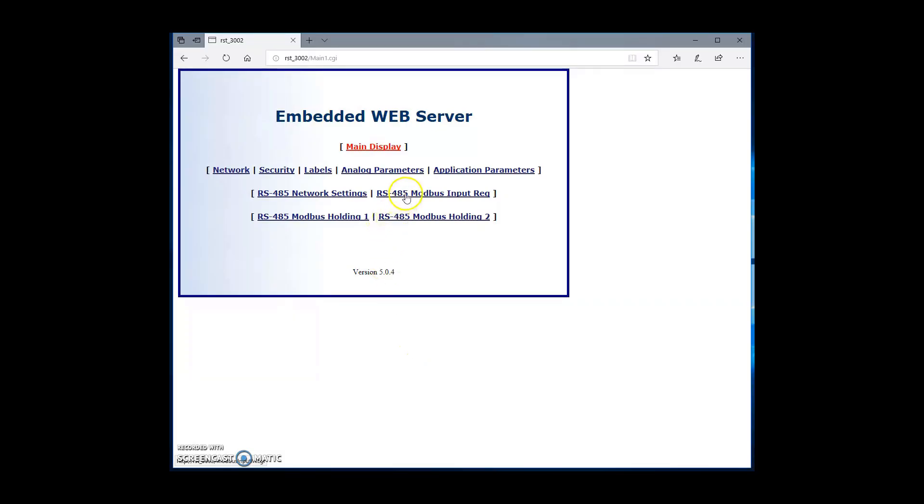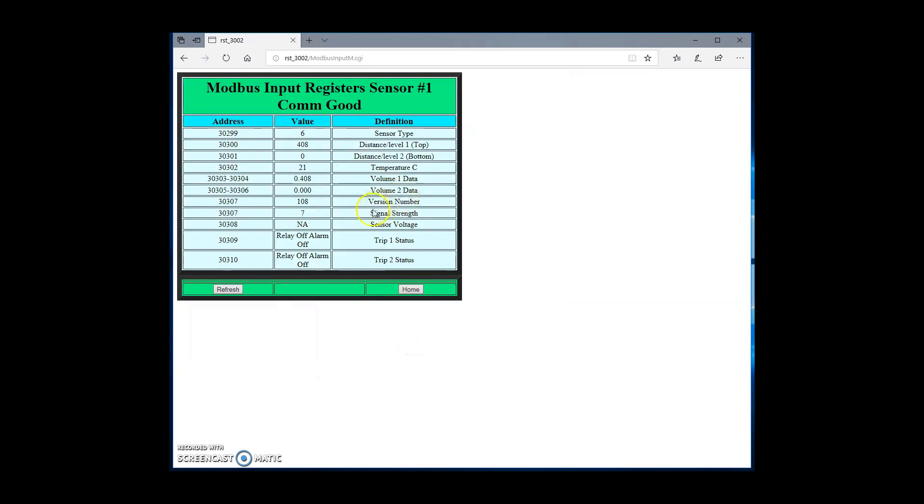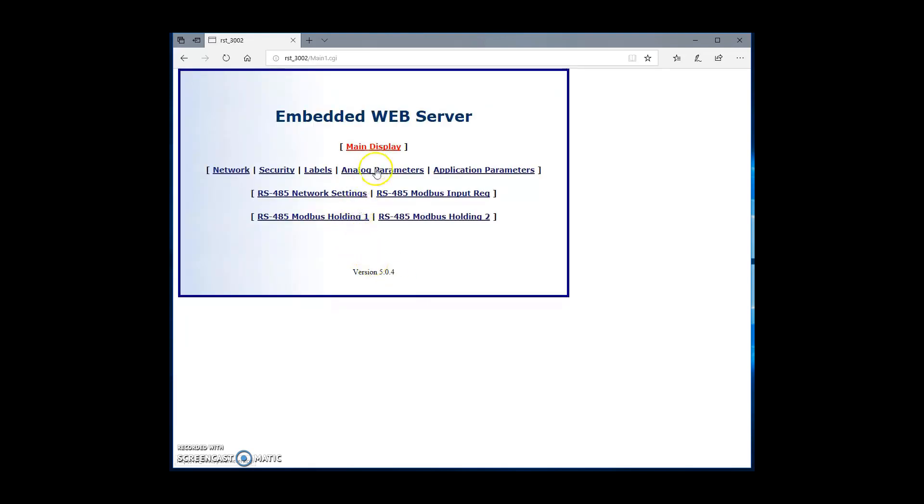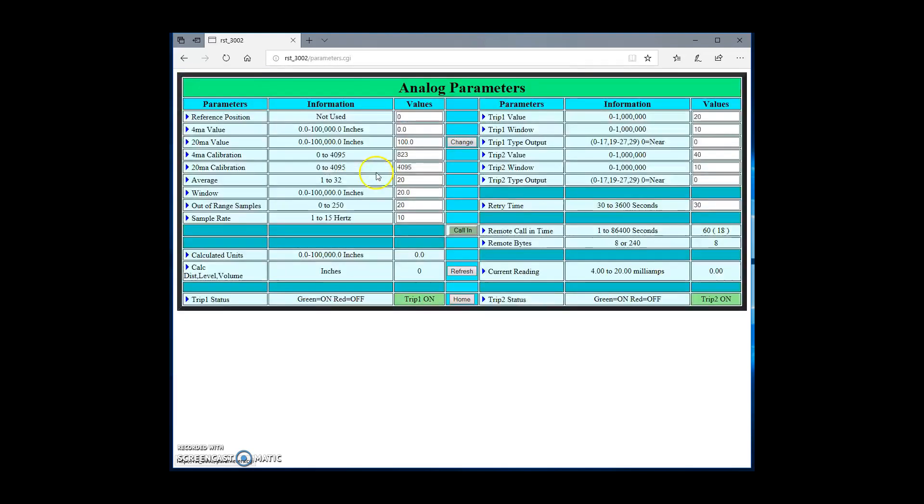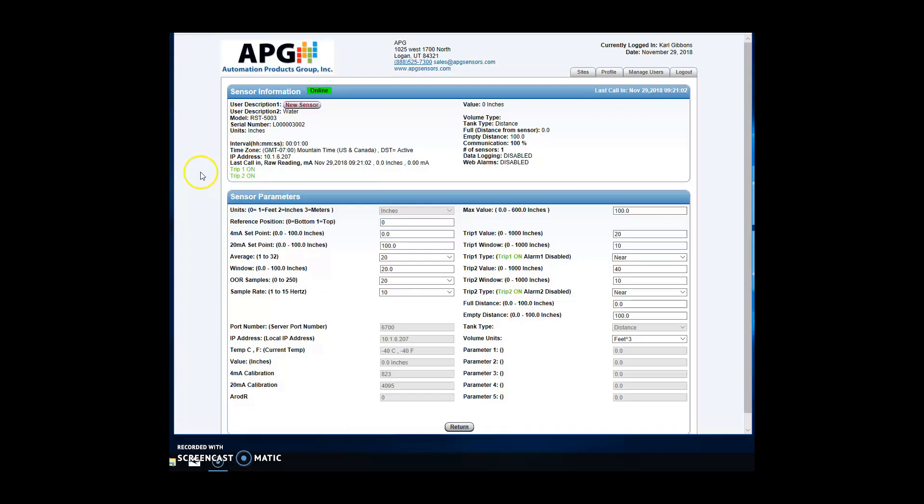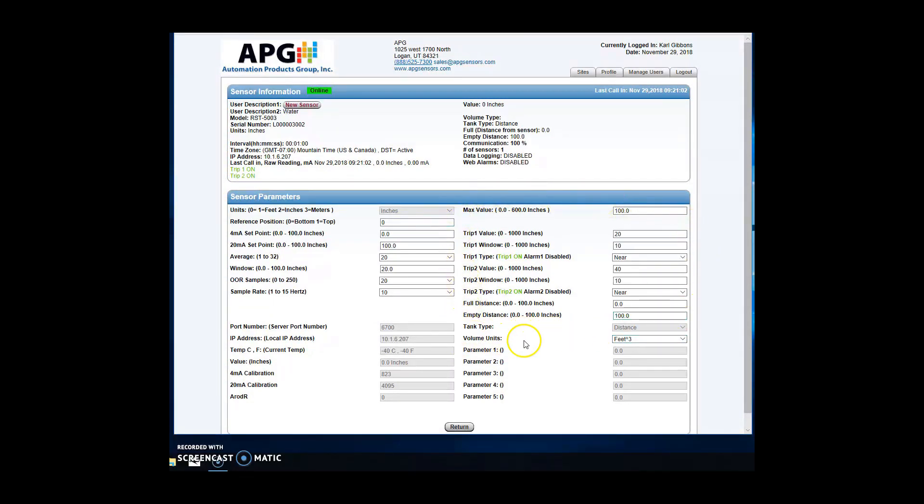Trip value, window, and type can be configured to create outputs in input registers 30309 through 30310. These are not electrical or mechanical triggers and so will not generate their own alarms. When interfaced by a web-enabled master controller with the Level and Flow website or another RS-485 interface, the interface can be set up to trigger alarms from these input registers.